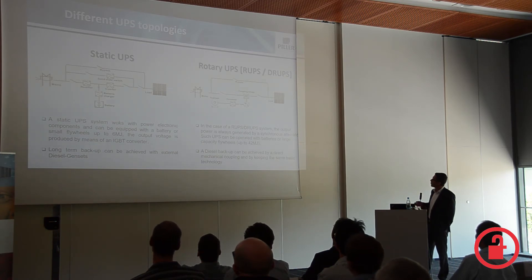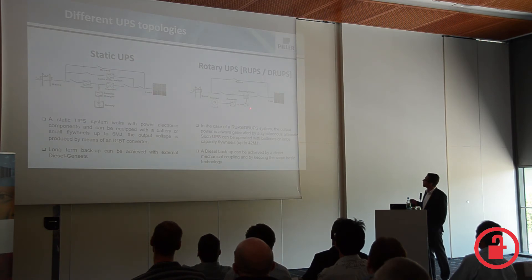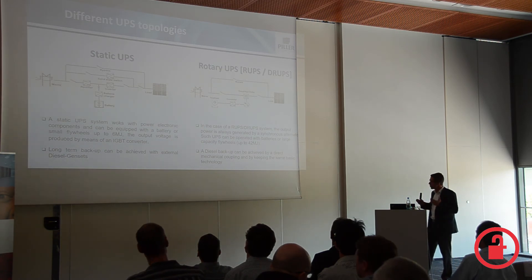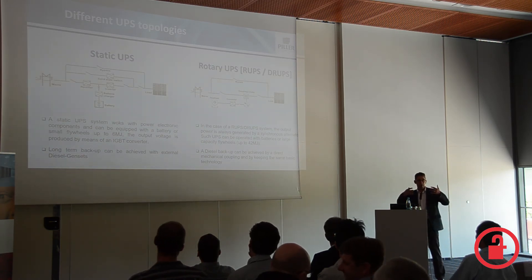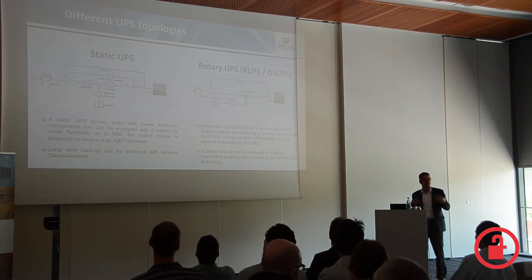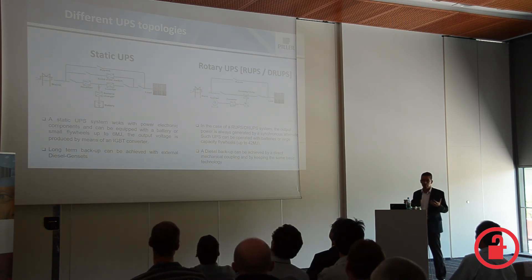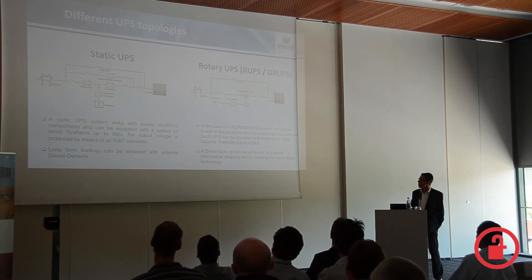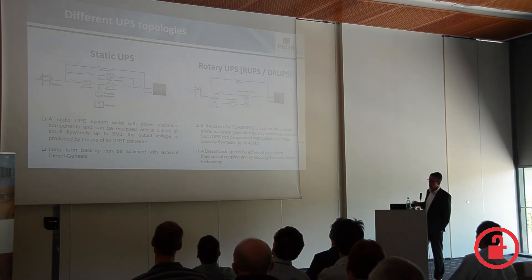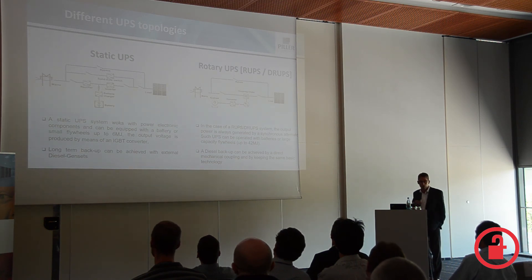On the other hand, we have a technology called the Rotary UPS. This is based on the functionality of a combination of a motor and a generator. These two engines are combined nowadays in a so-called Uniblock machine — a single set of rotating parts carrying two windings inside: the motor winding and the generator winding. All of this is connected via a choke to isolate the mains from the load. So what we see here are more or less electromagnetic components.